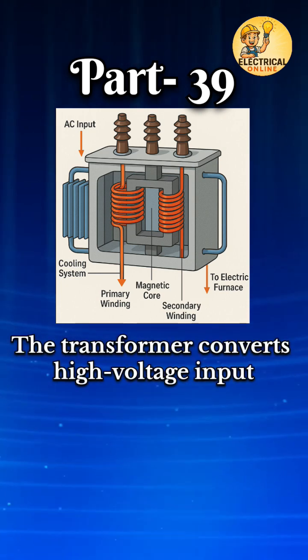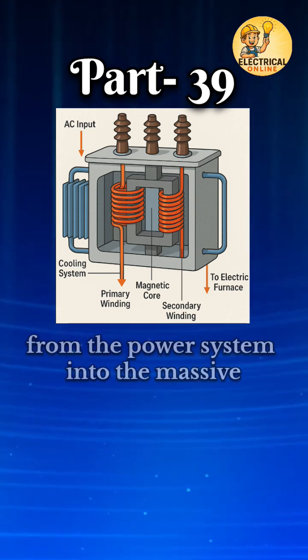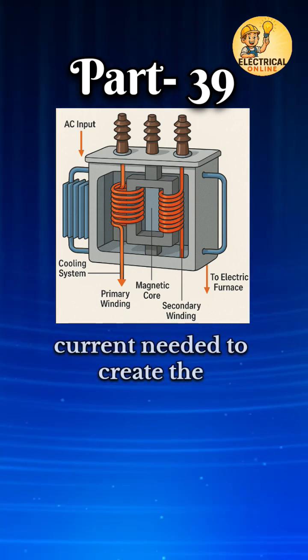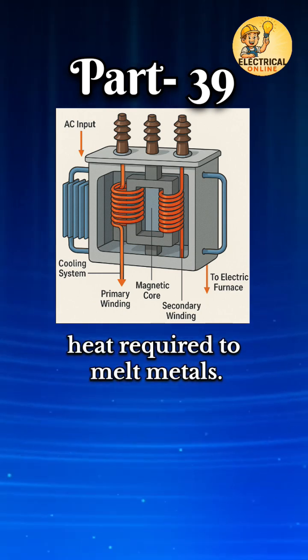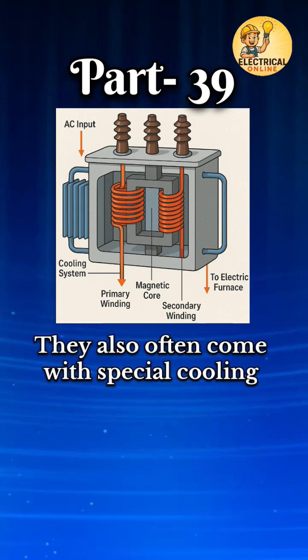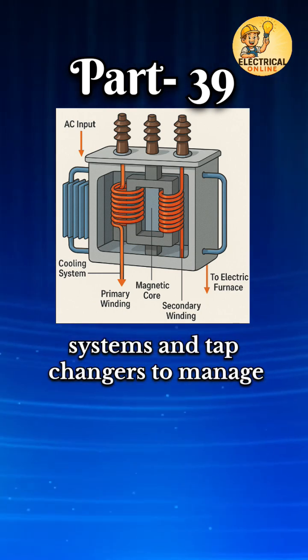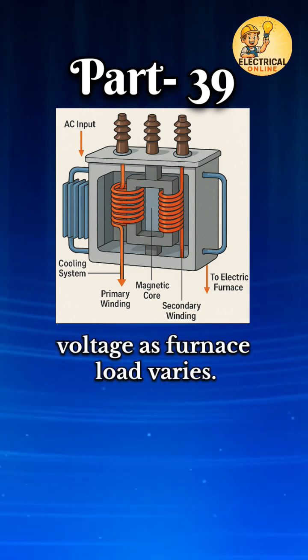The transformer converts high-voltage input from the power system into the massive current needed to create the heat required to melt metals. They also often come with special cooling systems and tap changers to manage voltage as furnace load varies.